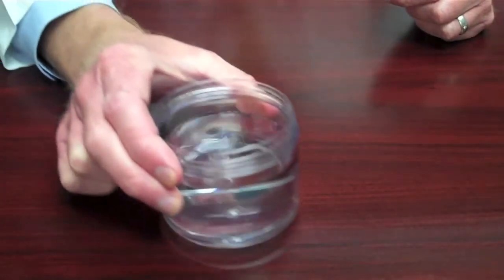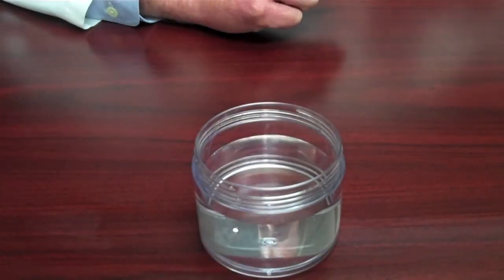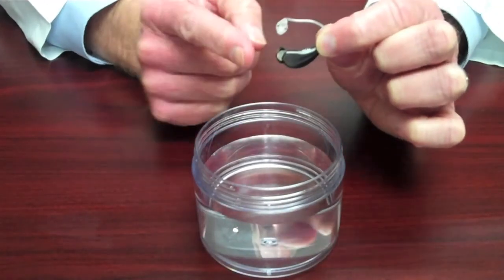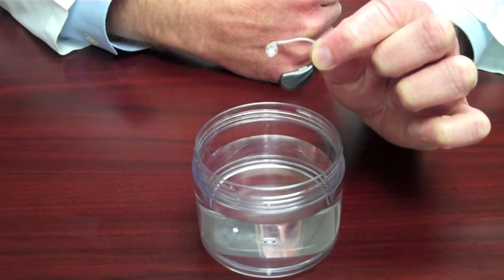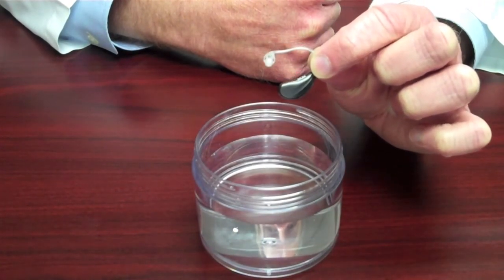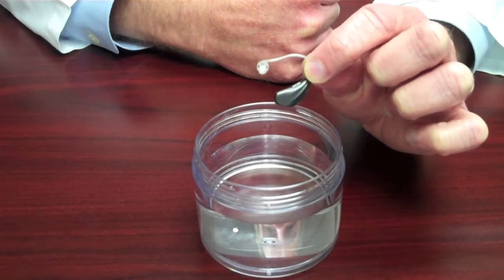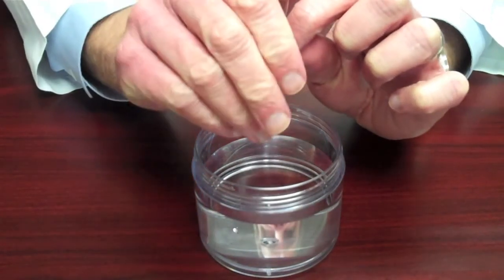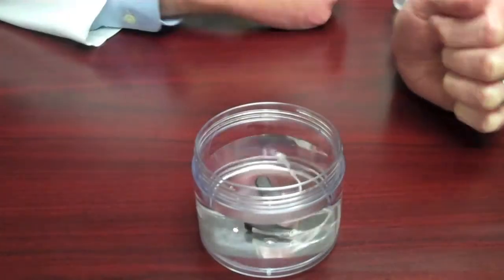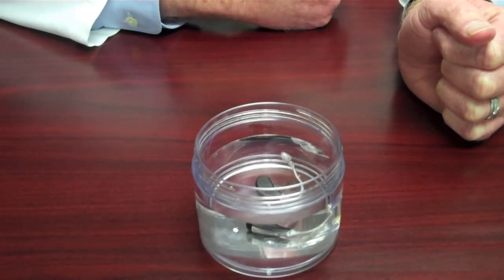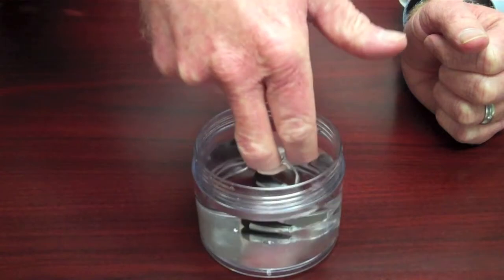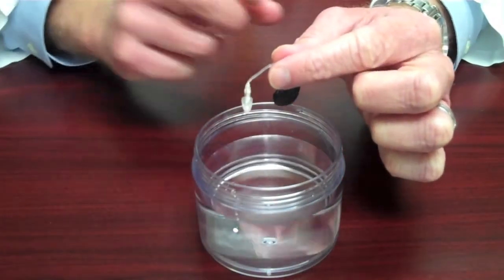Waterproof tissue is fun, but really we want to know how does it affect the hearing aid when the hearing aid is exposed to the elements. This is the Starkey Xino, and I'm going to close that up and turn it on. It's got a new battery in it. There we go. You could hear I've got the feedback canceller turned off, so it's whistling nice and loud. And I'm just going to go ahead and drop that in the water, and I could still hear that going. But all of the ports are exposed. The microphone's exposed, the speaker's exposed, the battery cover. All of that's completely underwater, and we can see that that's still working.